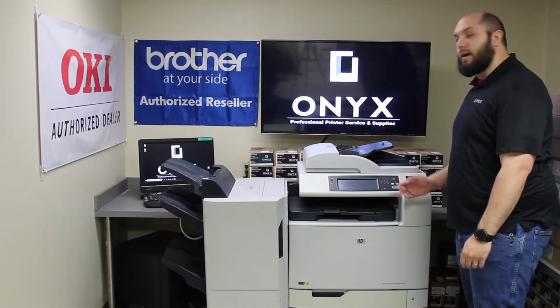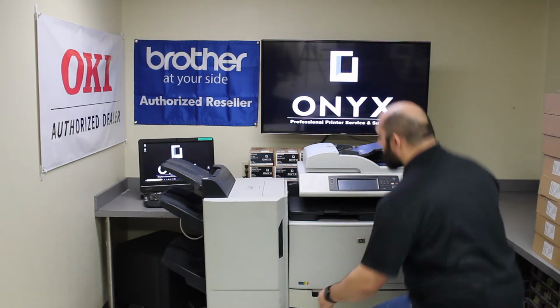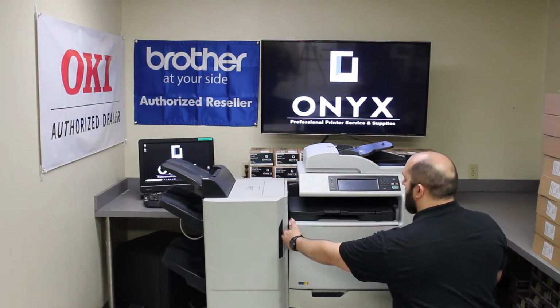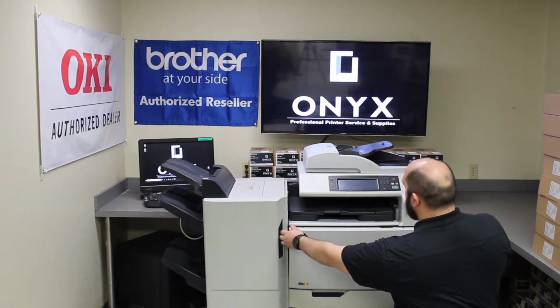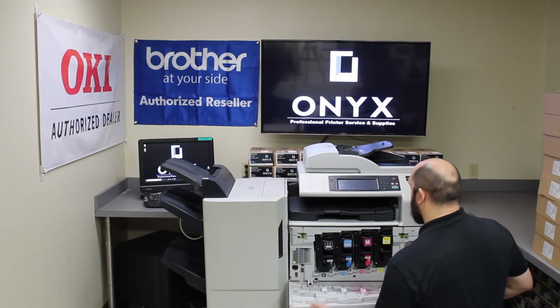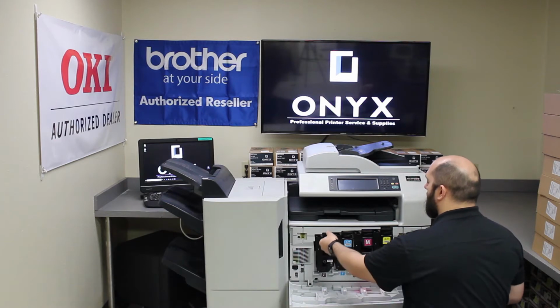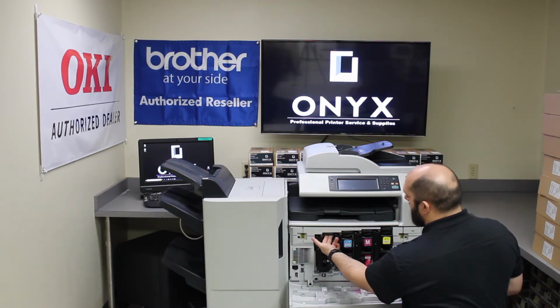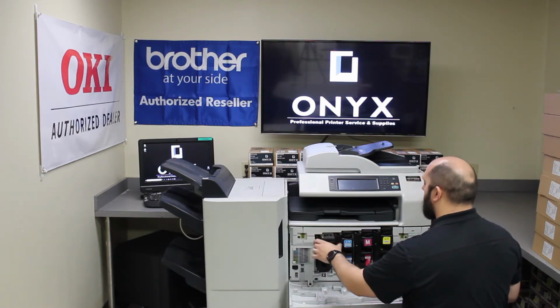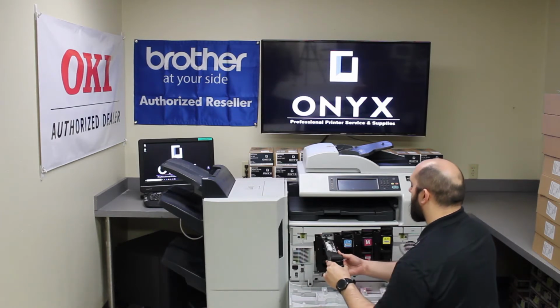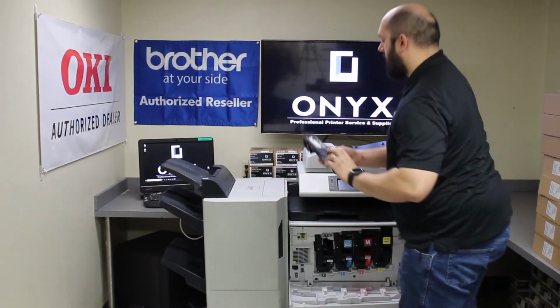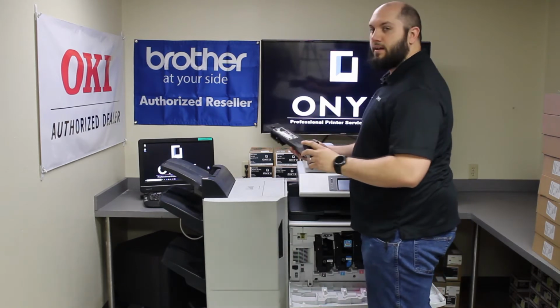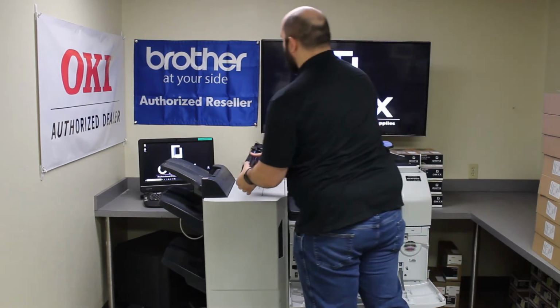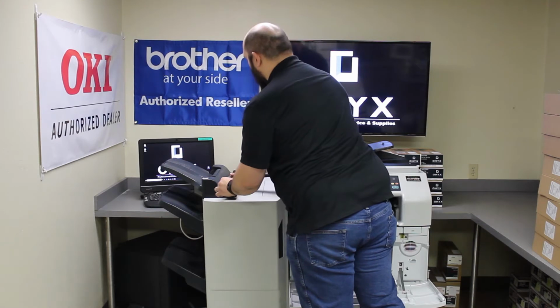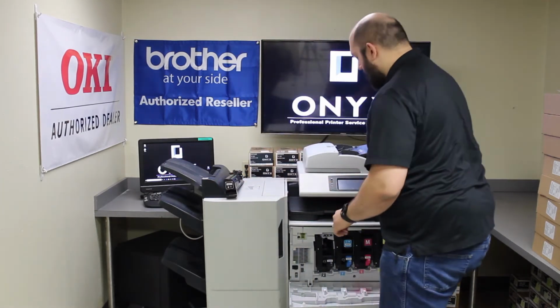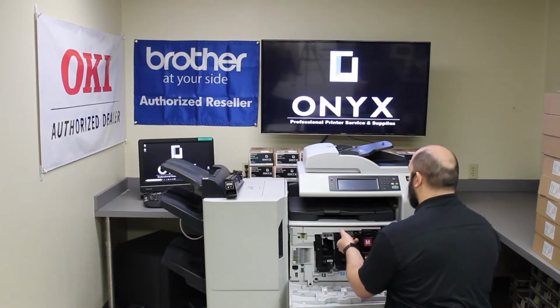Wait for the machine to actually power off, and then we're going to go down and you're going to grab the side of each handle, lower it down, and then remove one by one. There you'll see there's a little handle. Put your fingers into the little handle, slide the cartridge completely out, and then to set them down to avoid any kind of problems, I recommend turning them upside down on a clean, dry, flat surface. So we're going to do that for all 4 cartridges.